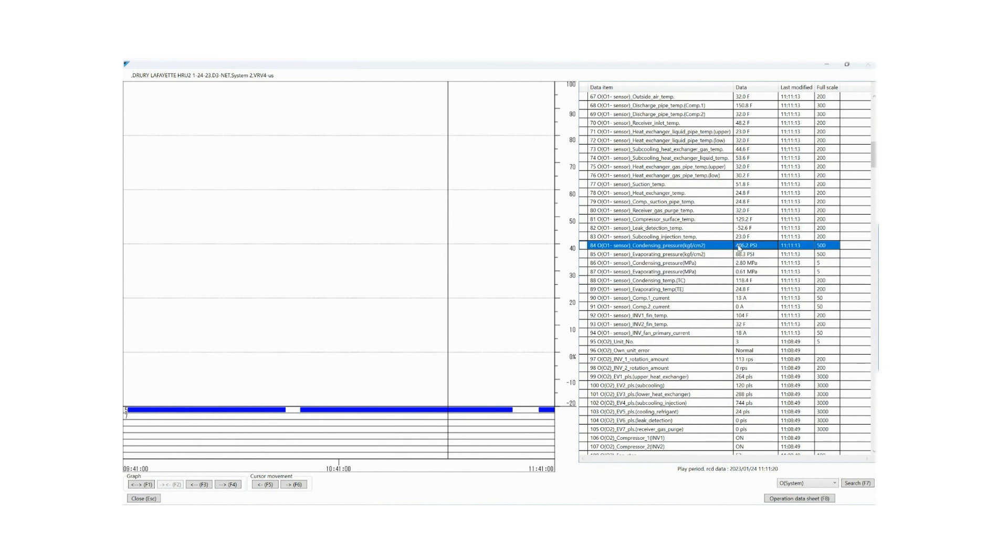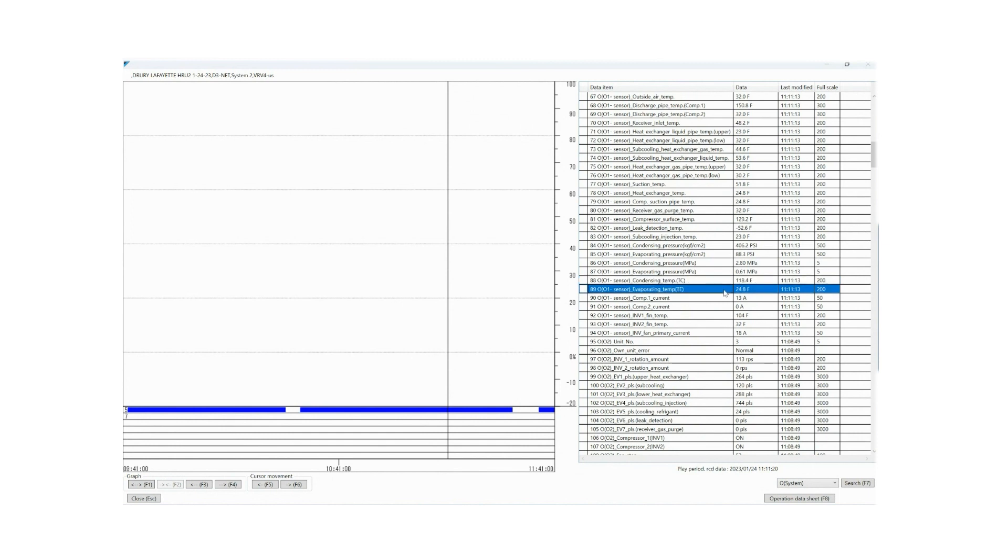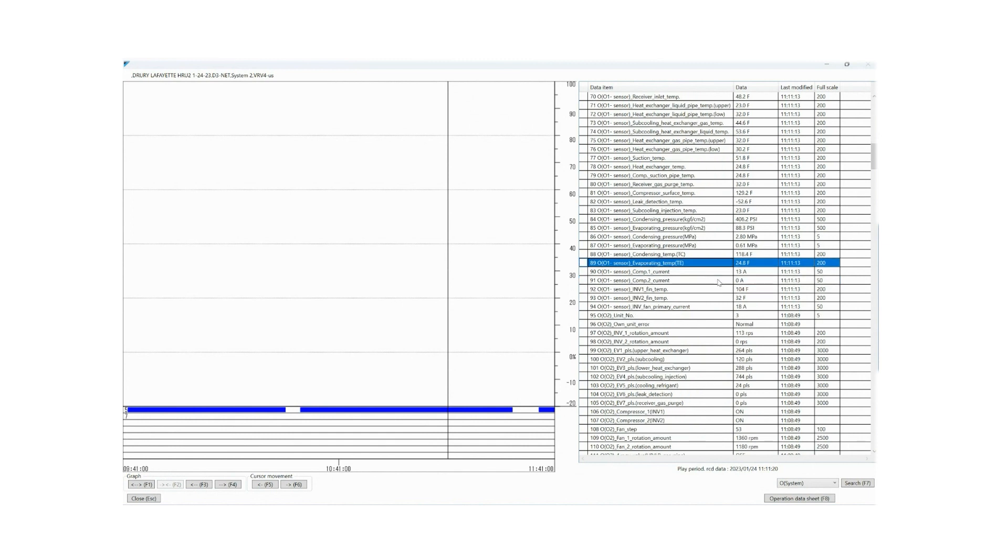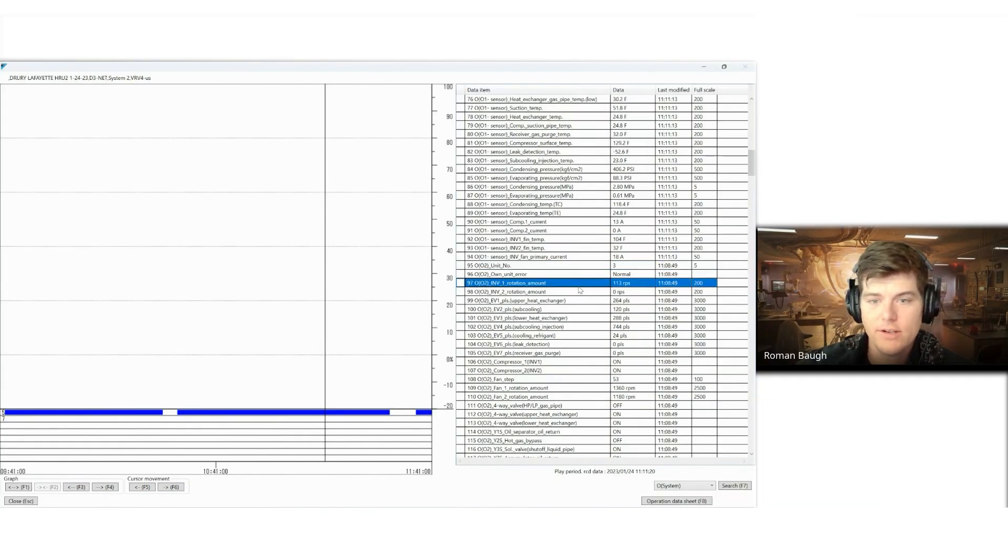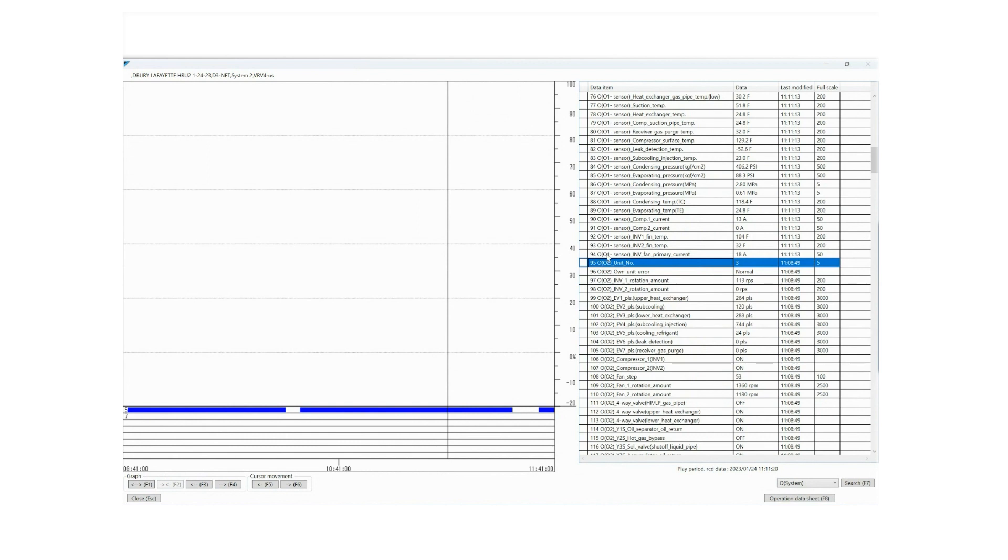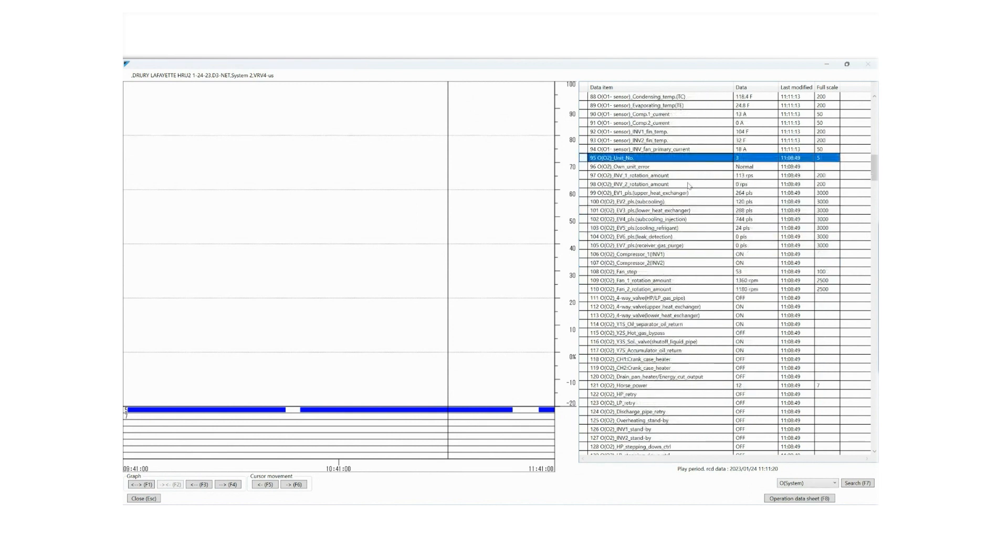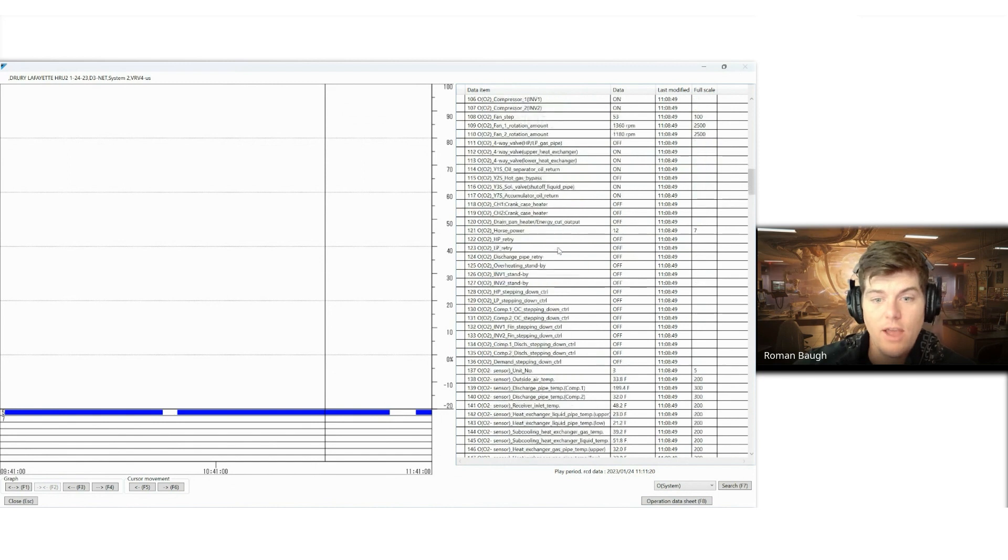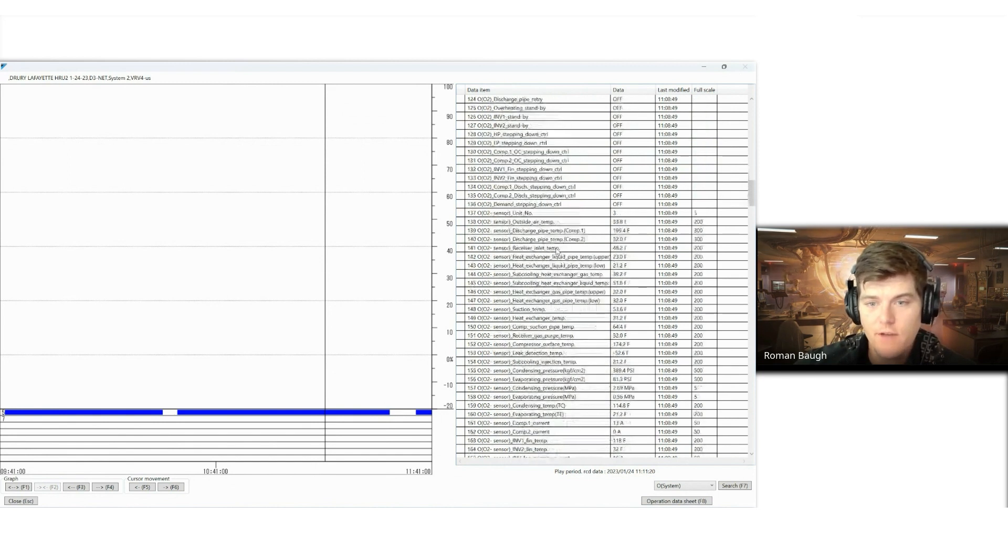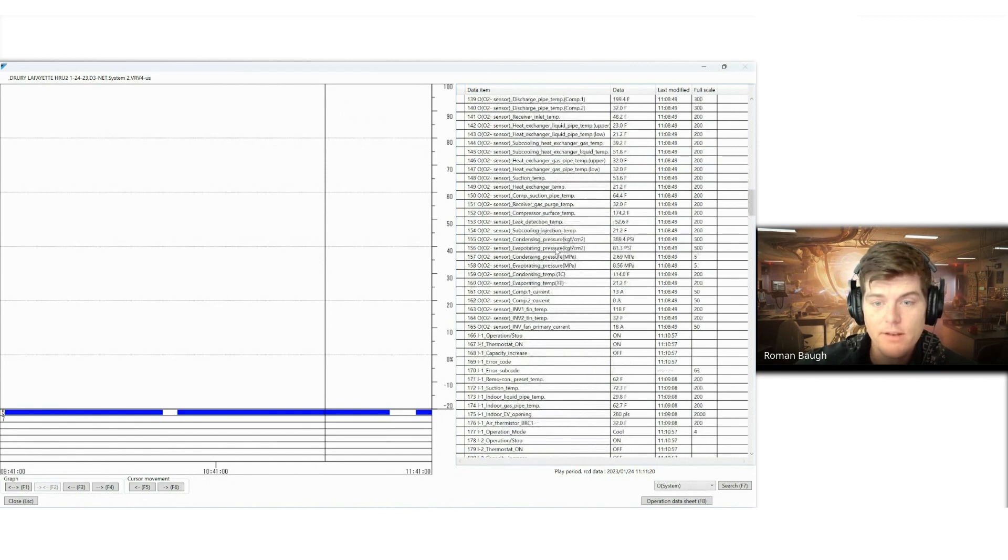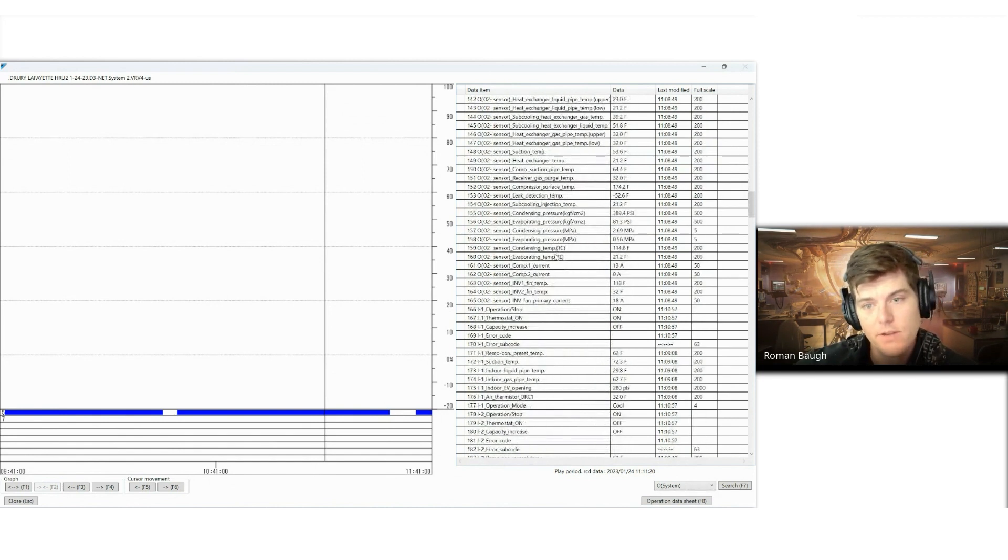Condensing pressure, evaporator pressure, condensing temperature. So this program itself takes this pressure and converts it to the saturation temperature for 410a, which for this, at 406.2 psi, is a condensing temp of 118.4. Same thing with the evaporator temp on the suction pressure. Compressor current, inverter fin temp. We're going down and down and down. And you'll notice, now I went from OU1 to OU2. That means that this has two modules tied together. Now I'm looking at the same exact data, but for the module next to the master. This is the sub-module.